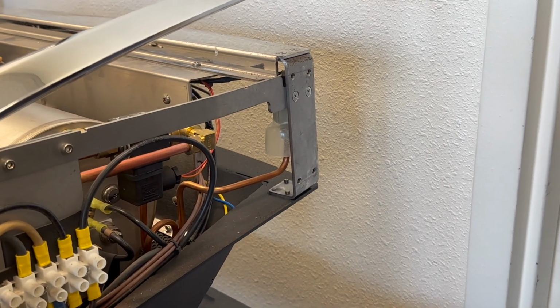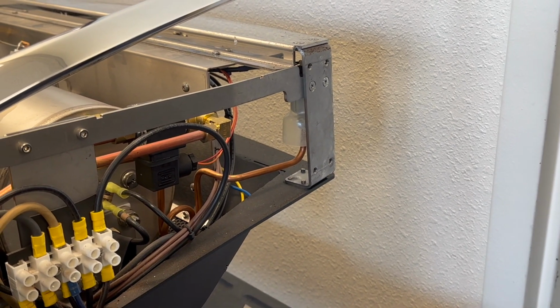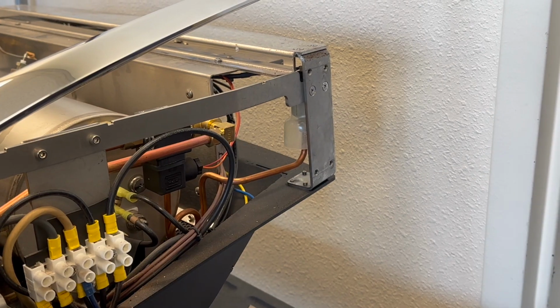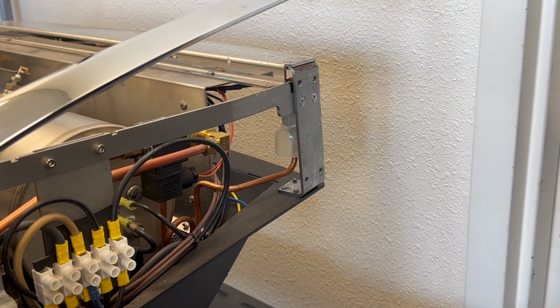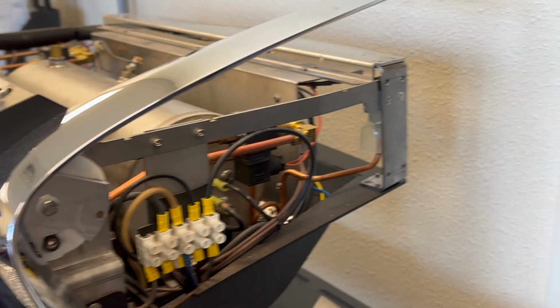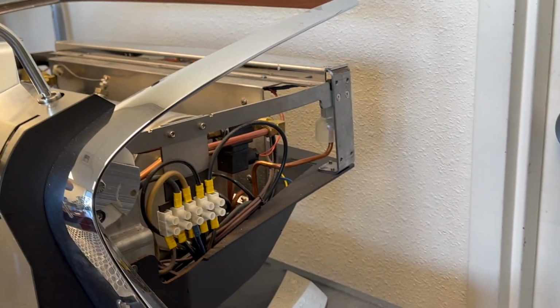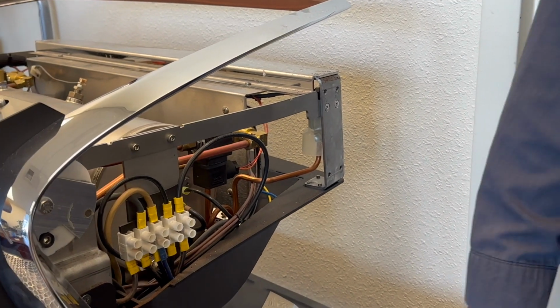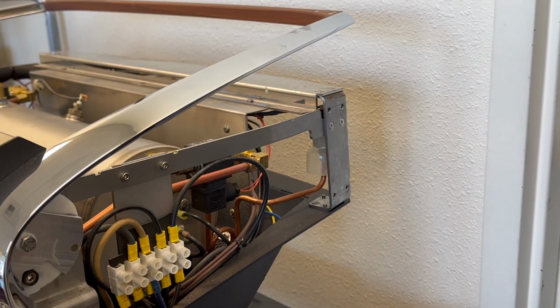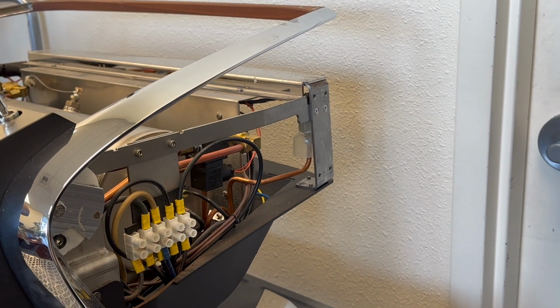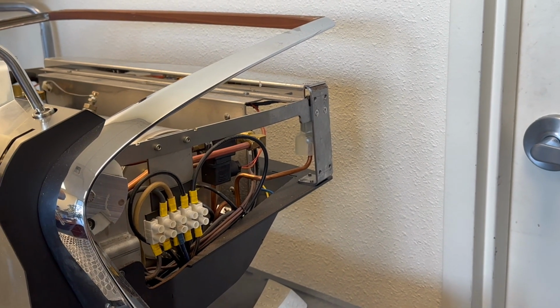So a PID is using a temperature probe, but a pressure transducer measures pressure, and that is an algorithm within the controller itself. Its reaction time is instantaneous depending on how it's programmed.